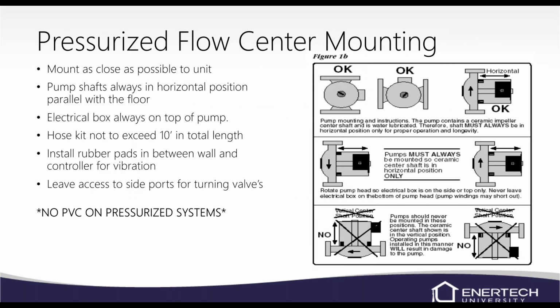Make sure if we've got a pressurized system that we're not using PVC and we're not using PEX. PEX has a huge pressure drop on it. If you use it, make sure that you're running your calculation for your pressure drop using the PEX. I just don't recommend it. But no PVC on pressurized. Sooner or later, probably sooner than later, it will break, then you're going to have a big mess. So no PVC.